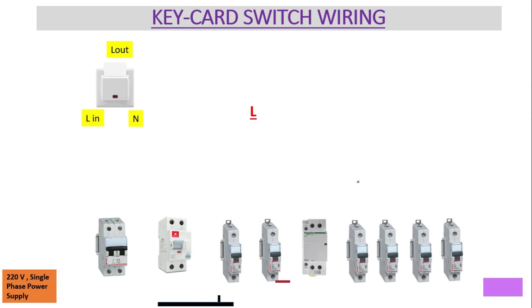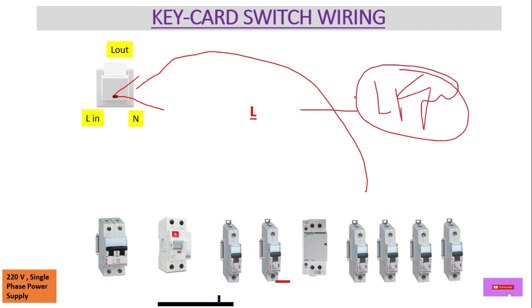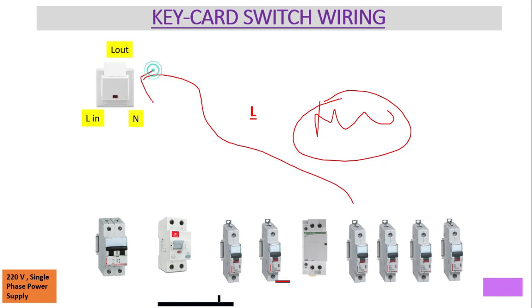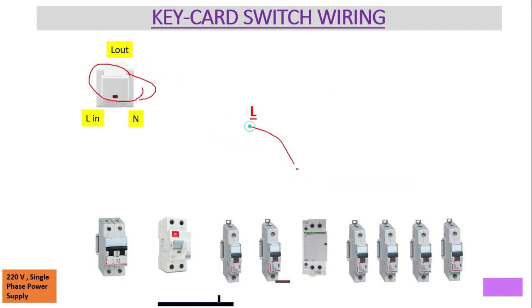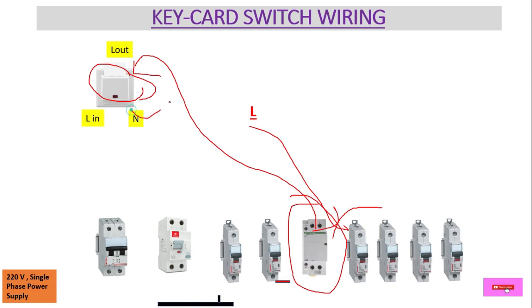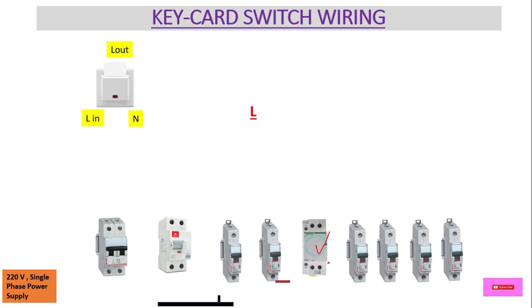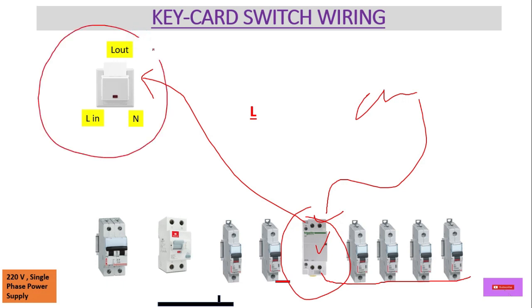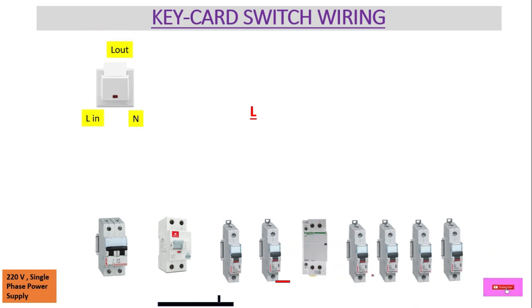This key card switch will operate the contactor. We generally do not put the load directly on the key card switch — for light loads we can, but for major loads like AC or kettles we cannot directly connect them to the key card switch. So it is better to use one contactor. The key card switch controls the contactor, and the contactor operates the load.